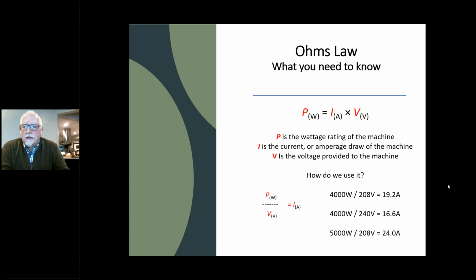So if you take the power of the machine, let's say you've got a 6,000 watt or a 5,000 watt espresso machine, if you divide that by the volts that are actually provided to the machine, that'll give you how many amps it's going to draw. And that amperage is going to tell you what gauge of wire you have to specify to the electrician to power the machine. It'll also specify what circuit breaker the machine has to be specified for. It means that if you're going into a client who's upgrading from a 2-group espresso machine to a 3 or 4-group espresso machine, and they think they can simply plug it in, that's not always the case. And Ohm's Law is where we figure out whether that new machine is going to fit on that old circuit.